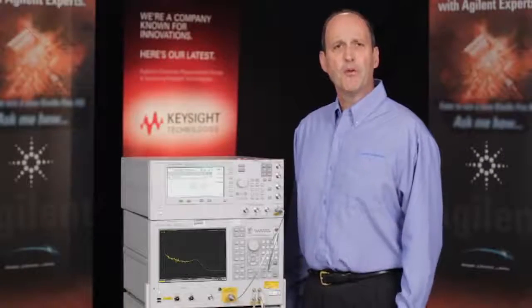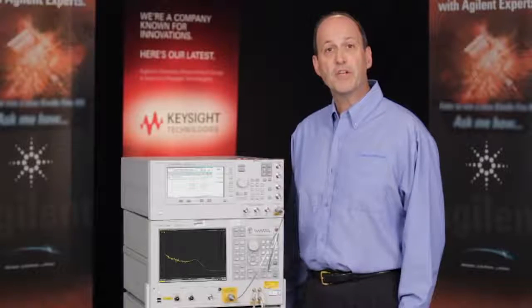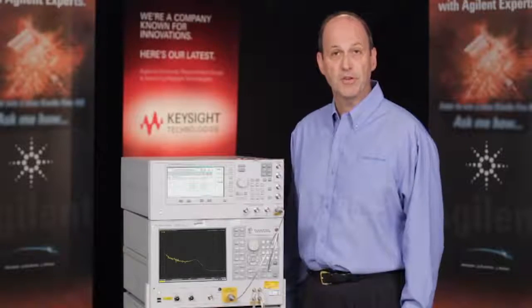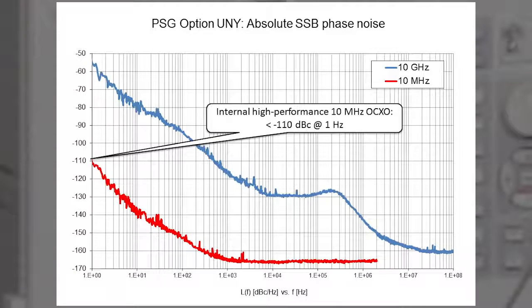If you're working on radar or electronic warfare applications, close-in phase noise for less than 1 kilohertz offsets from carrier is critical. At these offsets, PSG phase noise is dominated by the high performance 10 megahertz reference.